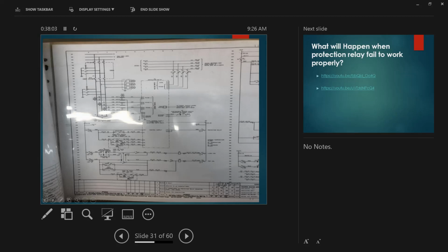Sorry, Francis. For the CT link, we usually don't do live online work. But let's say the client is happy that they don't want to turn off the CT's current, and if we wanted to use... my point is, let's say if you wanted to do live testing of the relay, what's the procedure to handle the CT? I think I would say no. As much as we have to do some isolation.